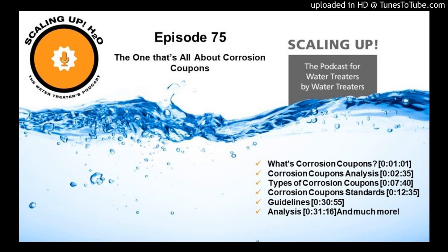Here's what I mean: the shorter the coupons are in the system, the more aggressive that system water is going to be to that coupon. Think about it, our job is to corrode the metal in a way that slows down the corrosion of that metal. We call that process passivation. If we put a brand new raw corrosion coupon in the system, it doesn't have the benefit of that passive coating, so we get a more rapid corrosion rate in the first couple of days.